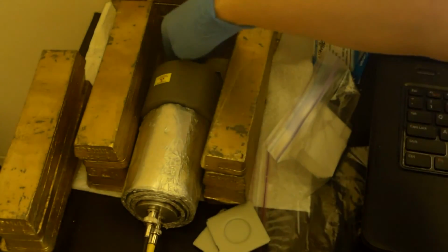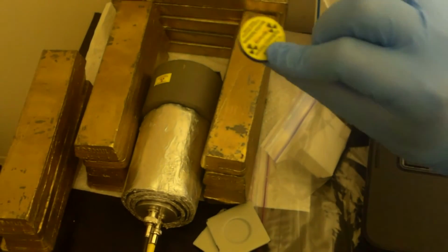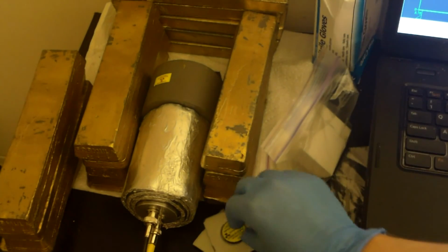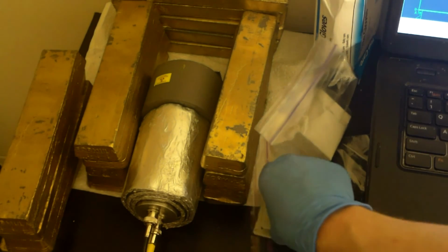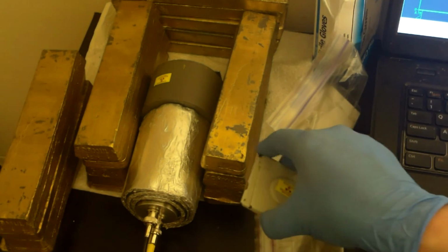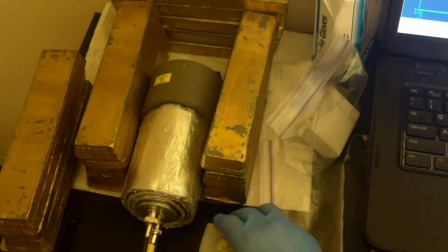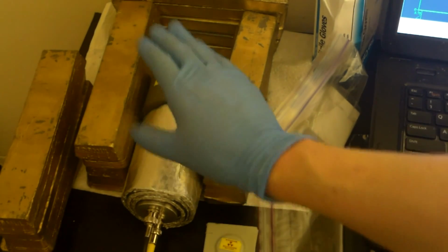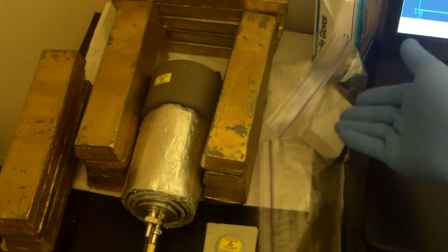So let's get rid of the calibration source first. This needs to be moved far away from the sample area. And when I mean far, I mean like far. And put behind lead too, because it can interfere with the spectrum. I'm going to put this right here, but I'm going to move it away before we do the actual test, because if you just put it right beside the unit, this will pick up a Cesium-137 peak that you will think is in the sample, but it's not.